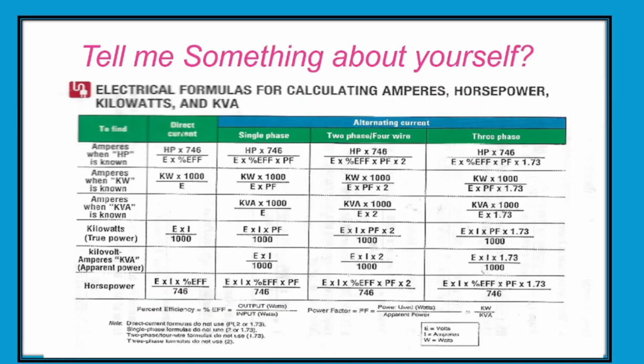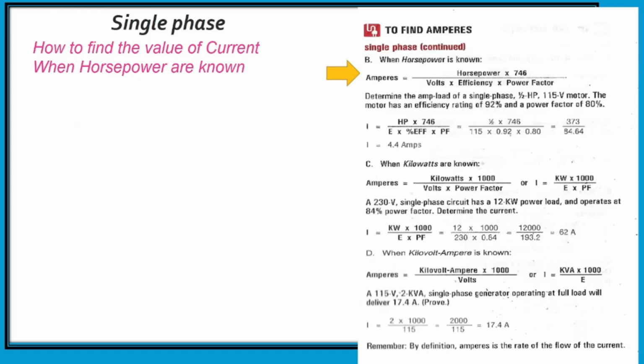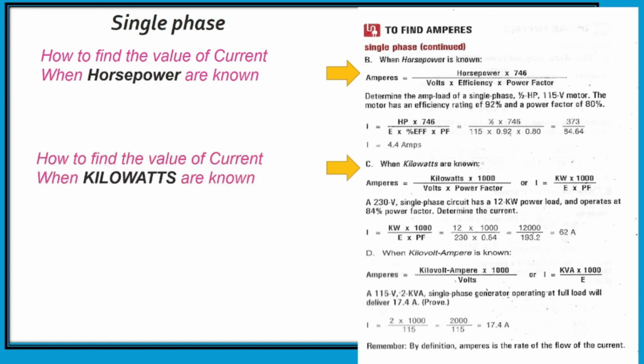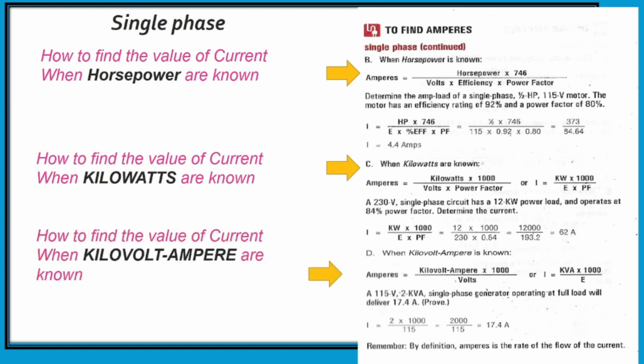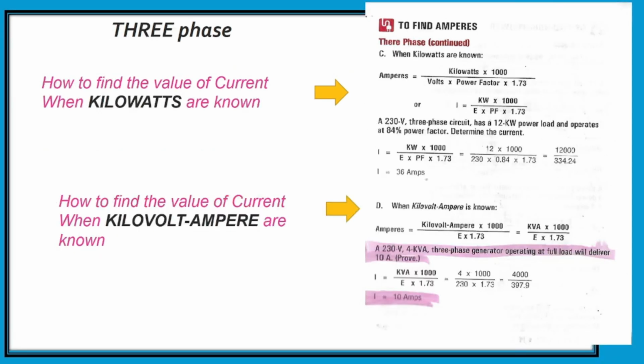The next one is the electrical formulas for calculating amperes, horsepower, and kilowatts. We have an example here of how to find the value of current. Look at it, just pause the video. And to find the current with known kilowatts. And to find the value of kilovolt amperes, this is for single phase. And this one is for 3-phase. The only difference between single phase and 3-phase is the square root of 3.